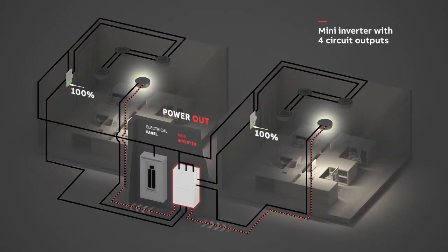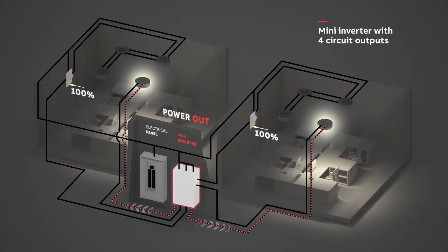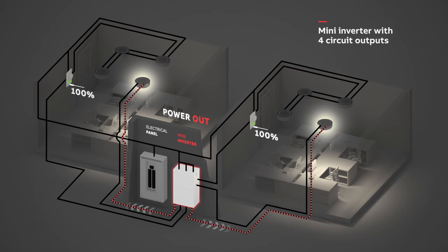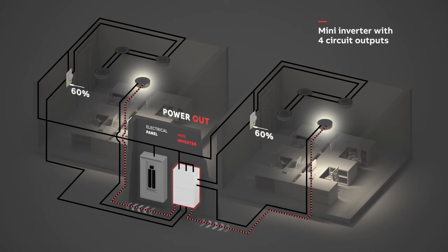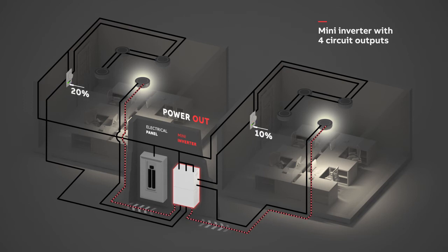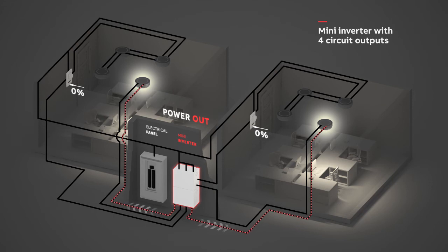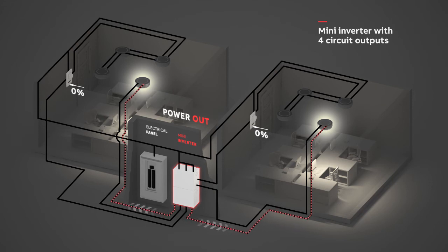When the main power goes out, the Mini-Inverter will bypass the dimmers, so that even if a dimmer is off or down, the lights wired as emergency lighting will turn on at full brightness, powered by the Mini-Inverter.